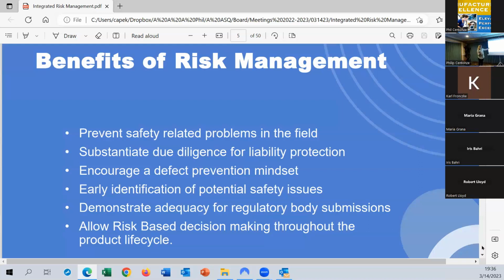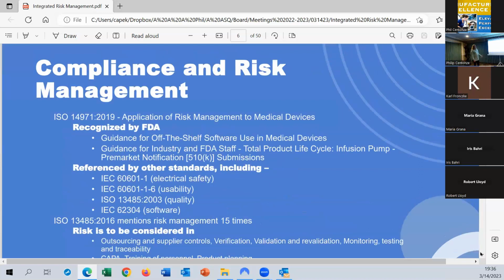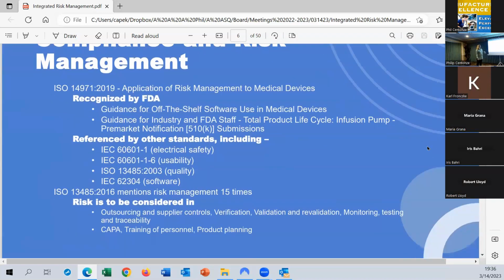It can cause liability suits, so you can lose a lot of money there. And you have to also have a risk management process in order to demonstrate adequacy to regulatory bodies. For medical devices, there is one particular standard, ISO 14971-2019, which is recognized by FDA, and pretty much if you're going to sell products in the US or in Europe, you're going to be using the standard.